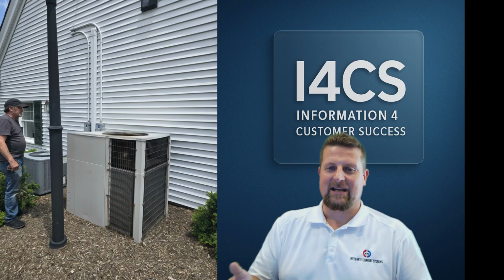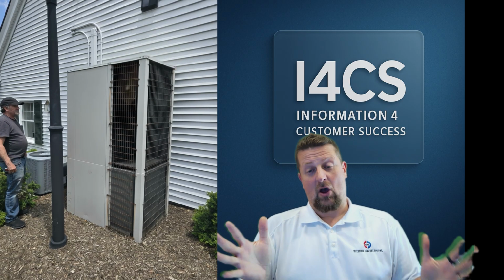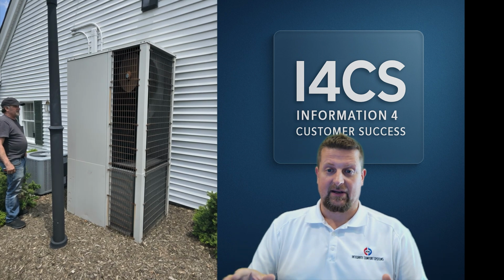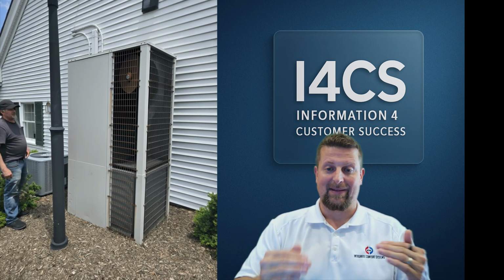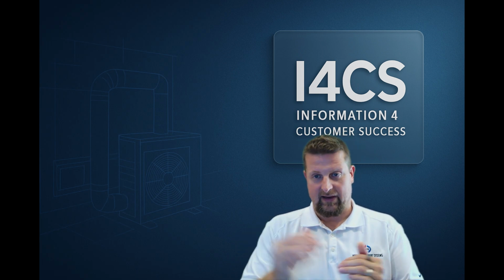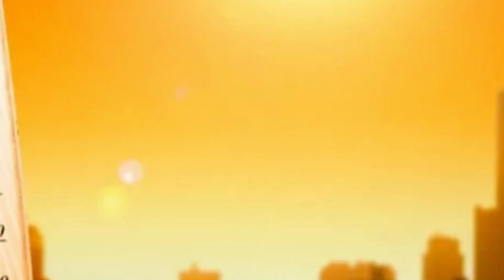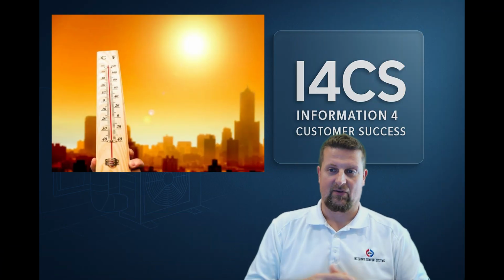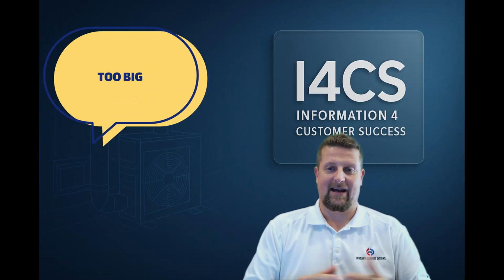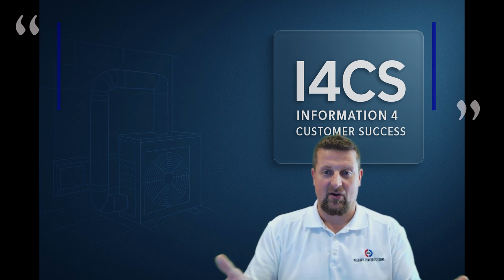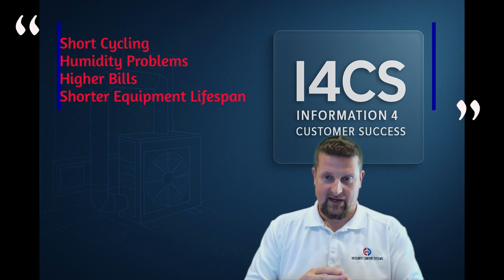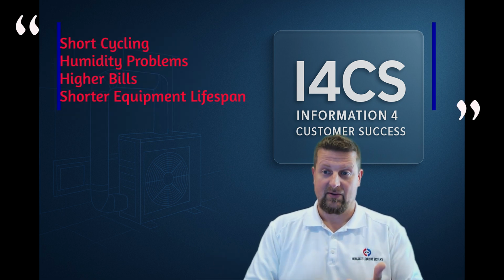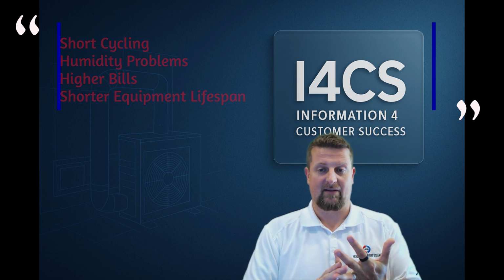Now, Chris, why don't we just design them bigger so I have more AC, right? Well, that's not the correct answer. It's not one of these very black and white things. It's a very variable thing. If we oversize systems for those once a year heat waves, your AC would be too big for the 98% of the remaining part of the year. That causes short cycling, causes humidity problems, higher bills, and shorter equipment lifespan.